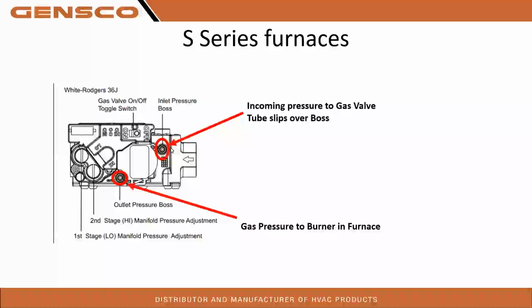So that's your inlet. So that's your incoming gas pressure. So that's where you're going to check for no more than 14, no less than 4.5 coming in, right? And then of course LP is going to change that a little bit. And then you have your gas pressure to the burner in the furnace itself. So it's actually what that gas valve will be feeding that burner. Okay, so that's where you're going to make your adjustments out of that guy there.